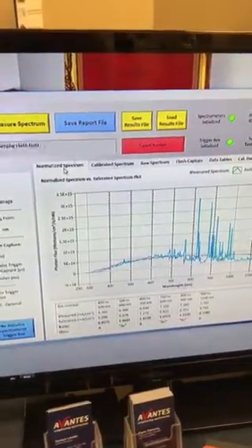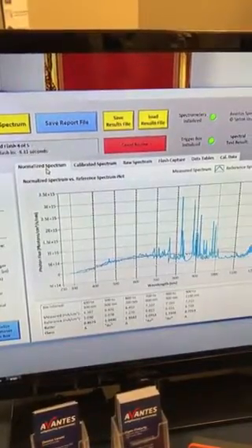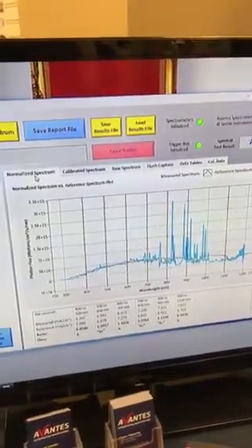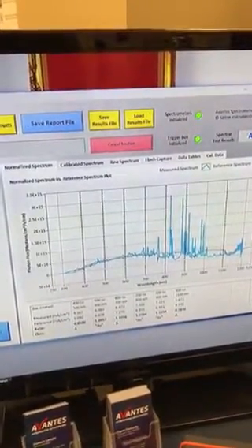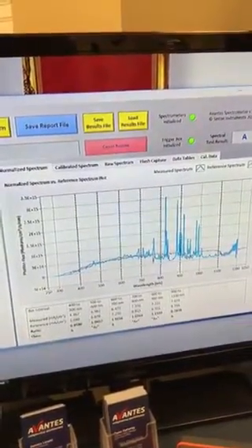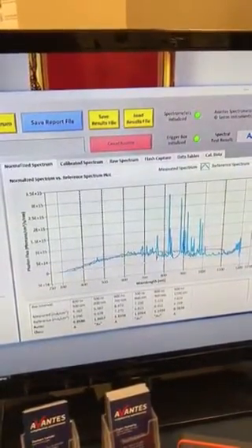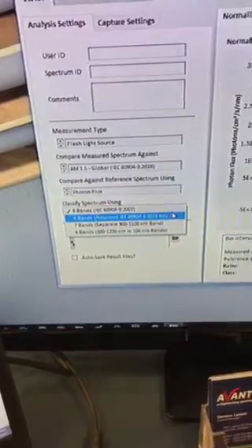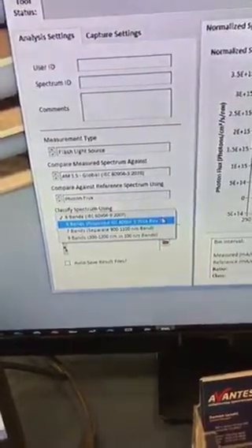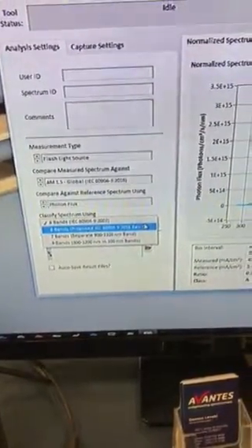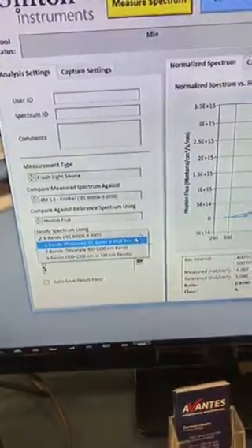the spectrometer software is measuring and then doing averaging of the different spectra, and one can choose whether you want to use an air mass 1.5 or some other global spectrum to compare against. You can also decide if you want to do the classification, what type of classification, whether you want the IEC 60904-9:2007 standard or the new proposed IEC 60904-9 2016 standard, which goes out to 1200 nanometers.